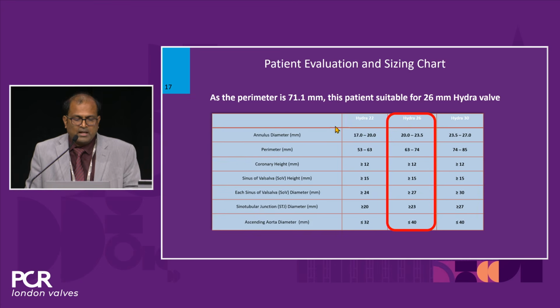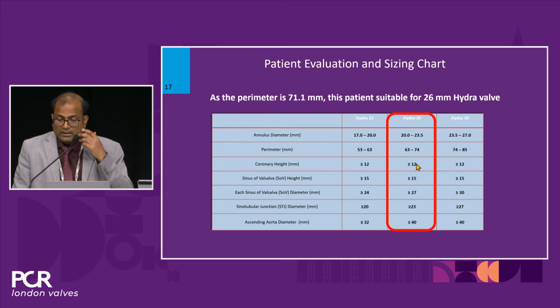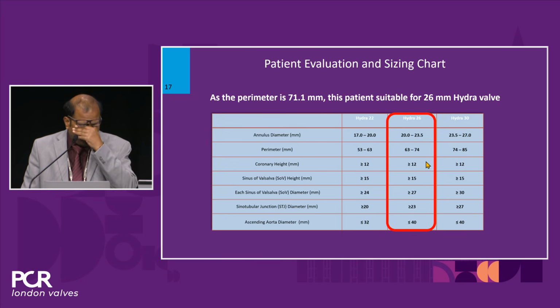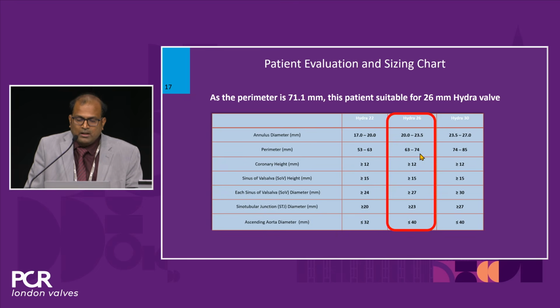This is the IFU suggested by Hydra. From 53 to 63 is the 22 valve. From 63 to 74, the 26 valve. From 74 to 85, the 30 valve. The other larger XL valves are in the picture now, and they are in the process of making intermediate valves too. There is a small difference between the numbers, the perimeter of Hydra as compared to the other platform. Keep it in mind. Don't extrapolate your knowledge of the other platforms to this platform.